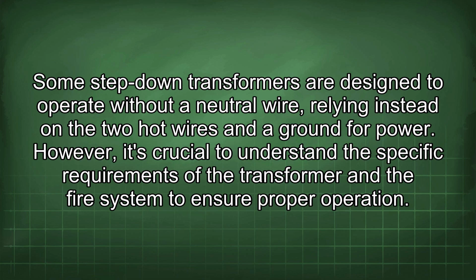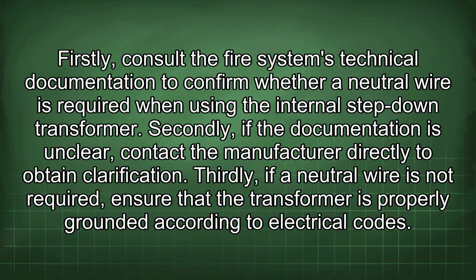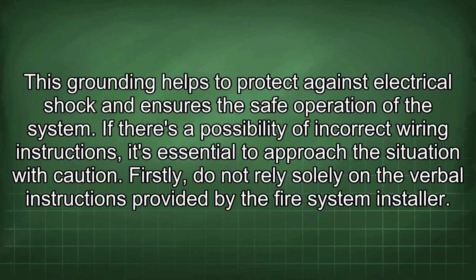ensure proper operation. Firstly, consult the fire system's technical documentation to confirm whether a neutral wire is required when using the internal step-down transformer. Secondly, if the documentation is unclear, contact the manufacturer directly to obtain clarification. Thirdly, if a neutral wire is not required, ensure that the transformer is properly grounded according to electrical codes. This grounding helps to protect against electrical shock and ensures the safe operation of the system.